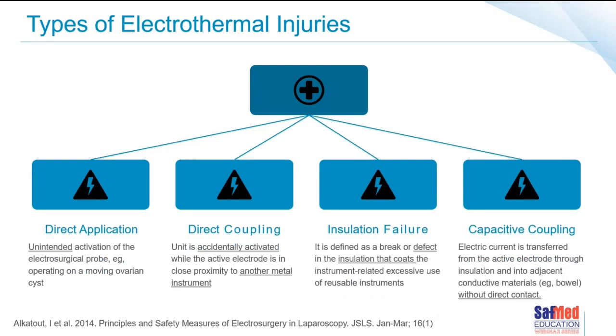There is the type of injury that can result from direct application. So that's when there's unintended activation of an electrosurgical probe. Maybe you're busy working on something and you accidentally end up standing on the pedal, and you activate and you burn a piece of tissue that you were not aiming at, or got some part that's moving and you accidentally catch that. It wasn't where you intended to be. Direct coupling, so that's a little bit different. That's when the unit is accidentally activated while the active electrode, so the tip of the diathermy at this point, is in close proximity to another metal instrument. And there the patient ends up burning via the second metal instrument.